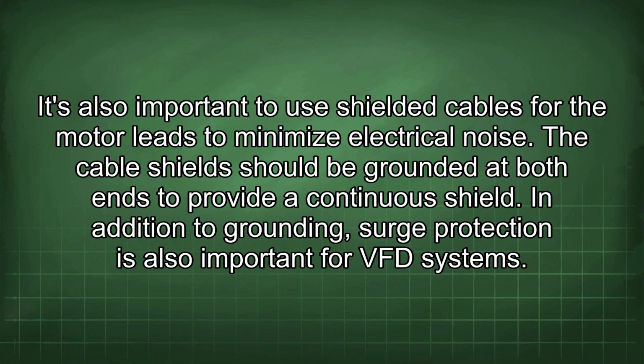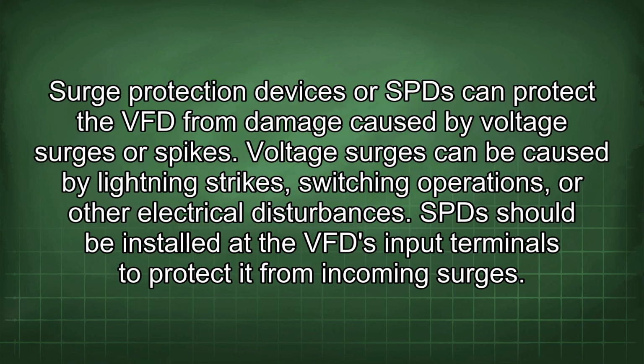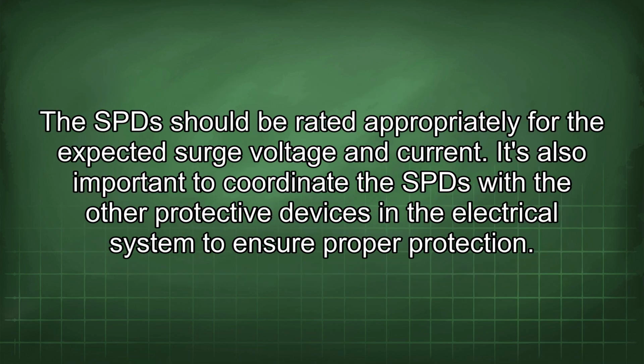In addition to grounding, surge protection is also important for VFD systems. Surge protection devices or SPD can protect the VFD from damage caused by voltage surges or spikes. Voltage surges can be caused by lightning strikes, switching operations, or other electrical disturbances. SPD should be installed at the VFD input terminals to protect it from incoming surges. The SPD should be rated appropriately for the expected surge voltage and current. It's also important to coordinate the SPD with the other protective devices in the electrical system to ensure proper protection.